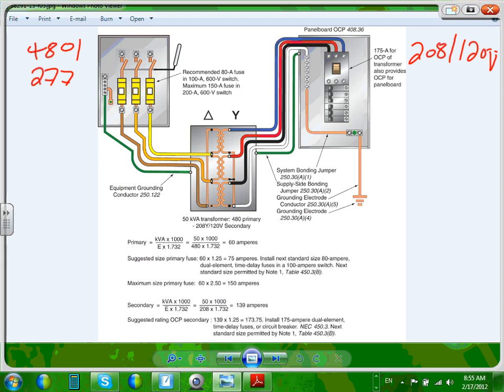So what you do, you have a panel or this huge disconnect next to the transformer, and you have a secondary protection, as you can see right here, secondary protection for the transformer, and you size the transformer. They're giving you an example, and I promise you we're going to do a lot of examples like this, guys. But before we go anywhere, I'm going to show you the transformer that they're using. I don't know if you see right here, it's 50 kVA. The primary is 480, like we said here, and the secondary is 208/120.